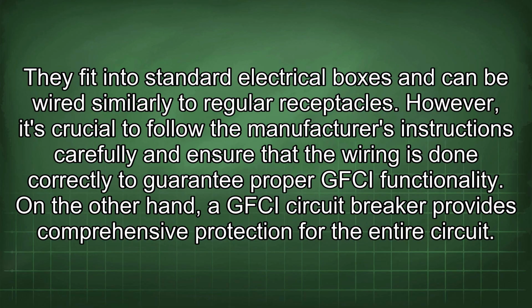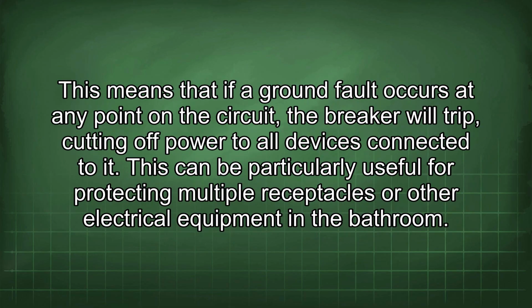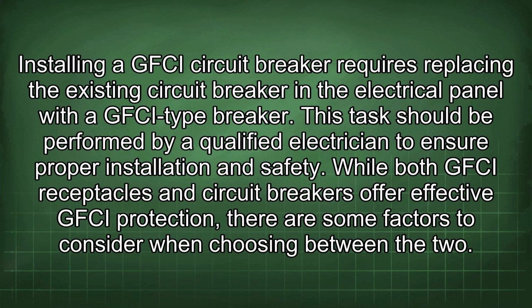GFCI functionality. On the other hand, a GFCI circuit breaker provides comprehensive protection for the entire circuit. This means that if a ground fault occurs at any point on the circuit, the breaker will trip, cutting off power to all devices connected to it. This can be particularly useful for protecting multiple receptacles or other electrical equipment in the bathroom. Installing a GFCI circuit breaker requires replacing the existing circuit breaker in the electrical panel with a GFCI type breaker. This task should be performed by a qualified electrician to ensure proper installation and safety.